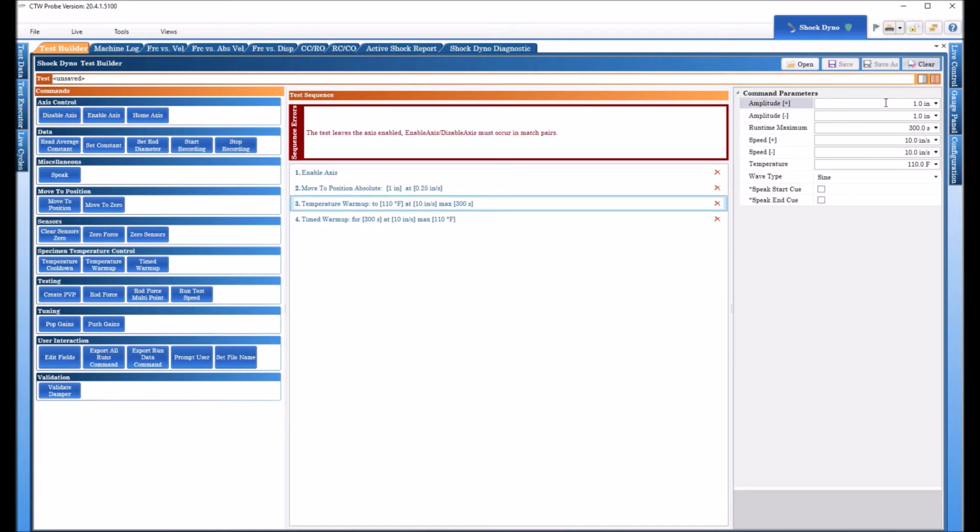Basically, the linear actuator, you can give it a positive amplitude and a negative amplitude, compression and extension from a mid-stroke, a midpoint of the run, a speed to run at, and basically a target temperature. I think typically we do a lot of 90 degrees. You get to decide how hot you want it to get, but this is the way you do your temperature-based warm-up. I'm going to get rid of that.